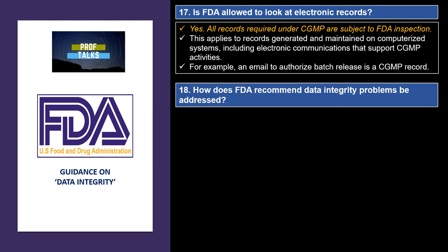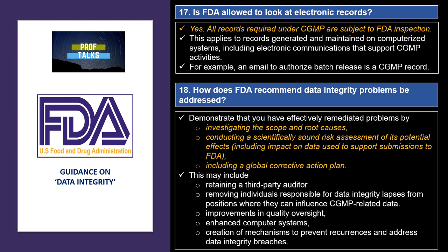The last question is: how does FDA recommend data integrity problems be addressed? FDA states that it should be demonstrated that problems have been efficiently remediated by investigating the scope and root causes, conducting a scientifically sound assessment of potential effects including impact on data used to support submissions to the FDA, and including a global corrective action plan.